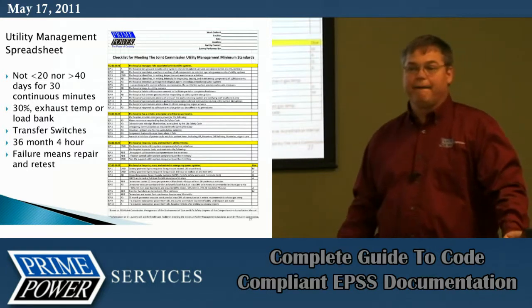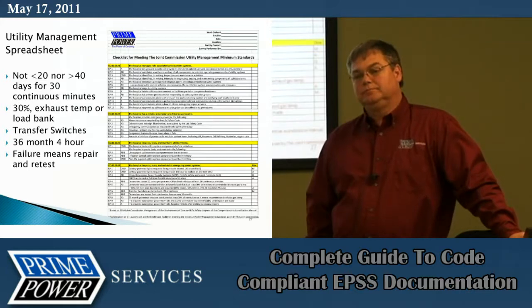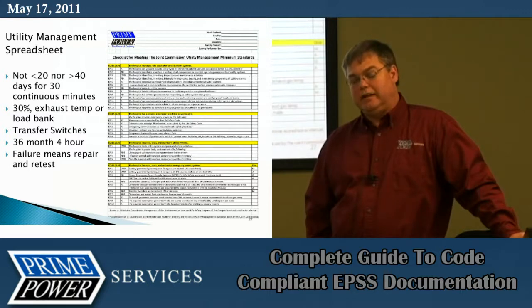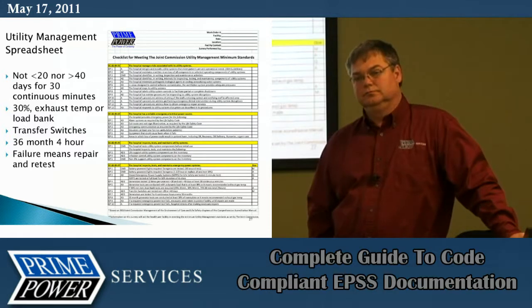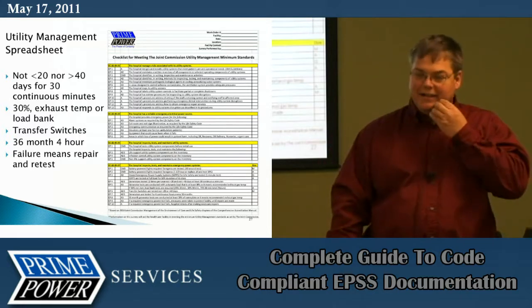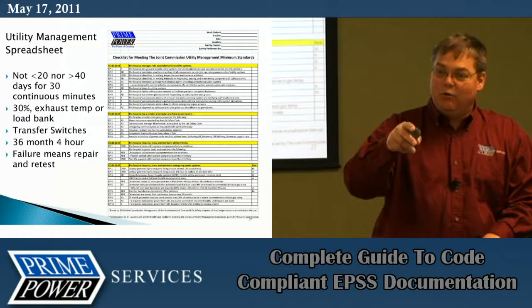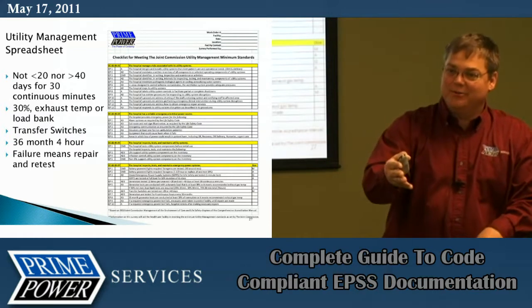Terry, let me ask you a question. Say you have 3 or 4 generators. What we're concerned about mainly is life safety. Right? Or the highest concern, I should say. If you have a portable generator that you can move around from area to area because you do not have any redundancy, and you just check it, there is no code requirement on something like that as to how often it has to be checked, is there? There is not in the way that you asked the question, but let me throw something in.